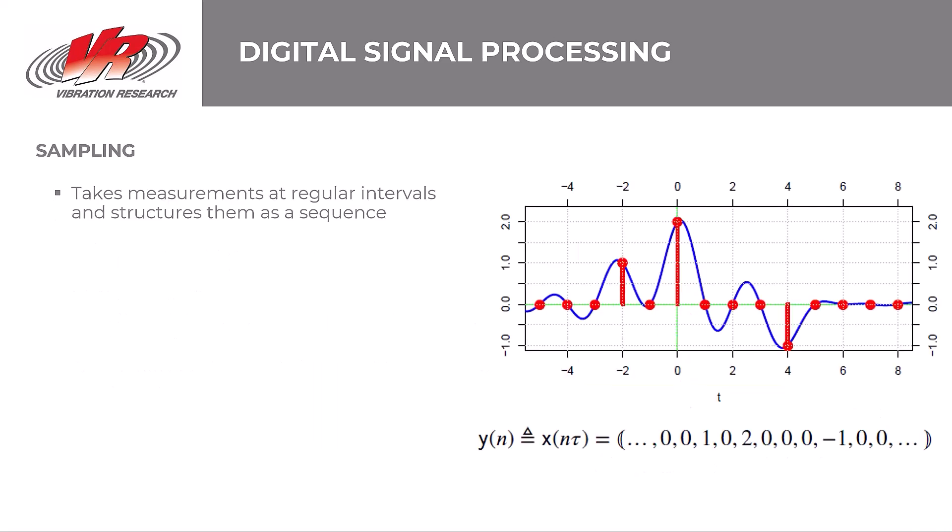So, now that the hardware has conditioned the signal, it can perform analog to digital conversion. Control systems can use sampling as a method to digitize a signal. Sampling takes measurements of a vibration waveform at regular intervals and structures the measurements as a sequence of values. After sampling, the control system applies filters specific to the test type. These filters are software programmable, and they are what we are going to concentrate our discussion on today. Now, each test type has different filters that we can use. Today, we'll go over filtering for the fundamental test types: sine, random, and shock.